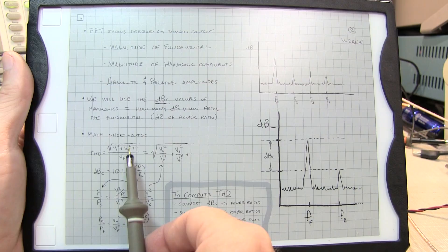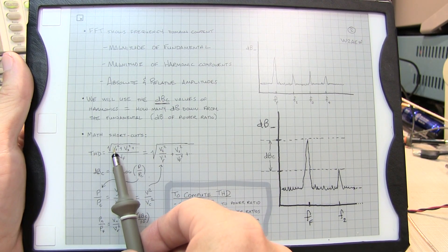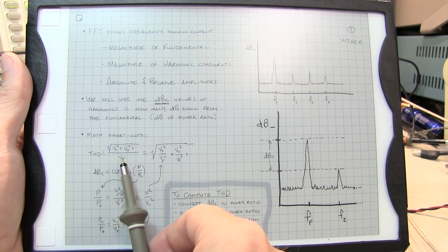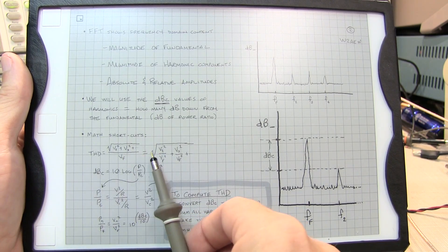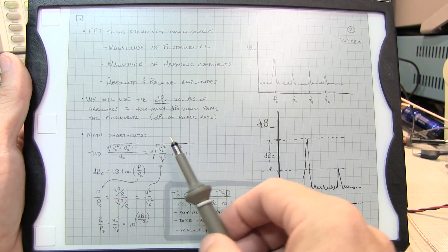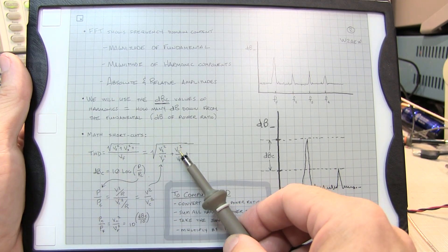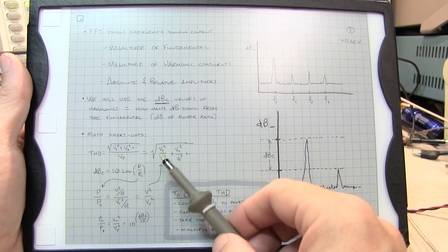If we take a closer look at the THD equation, again we've got the RMS sum of the harmonic RMS voltages divided by the RMS voltage of the fundamental. That could be expanded out to be the square root of the entire quantity of the second harmonic with respect to the fundamental, the third harmonic with respect to the fundamental. So you do this all individually, V squared over V squared.